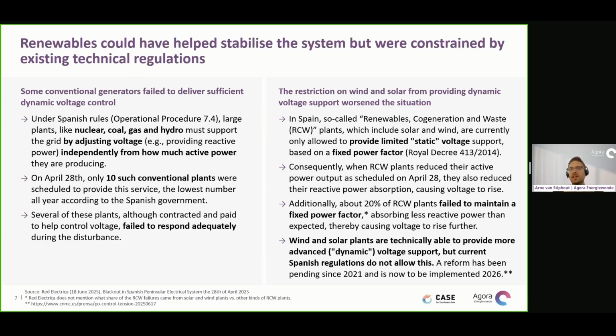These plants are technically capable of providing the more advanced dynamic voltage support, but current Spanish regulations do not allow them to do this. A reform that the TSO had proposed to the regulator to change this had been pending since 2021 and is now to be implemented in 2026. So what we see here in part is both grid operating practices, but importantly also policy and regulators, policymakers and regulators, not actually keeping up with the changes of the power system that is happening and the consequences this may have.